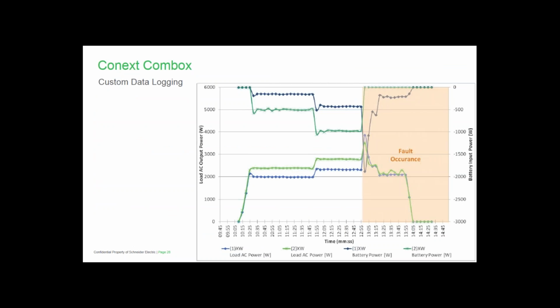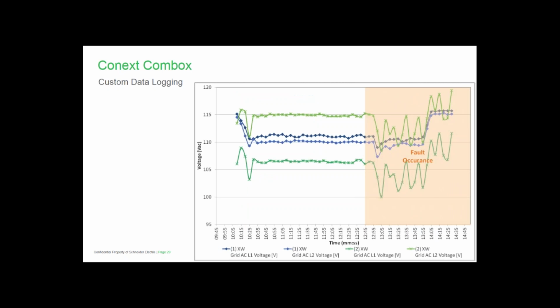This example shows a dual XW system with uneven discharge from 2 separate battery banks. The system was load shaving during this period. So we can see that in the upper portion we have the differential in bank voltages, and also the differential in battery bank power levels, as well as a differential in load power. So when we logged the AC voltage, it revealed a differential in AC voltage between the 2 inverters as a result of a bad connection. The problem was solved, resulting in more balanced sharing of the load between the 2 inverters. And by the way, this is just one example of the myriads of different parameters that you could monitor to troubleshoot a particular issue.